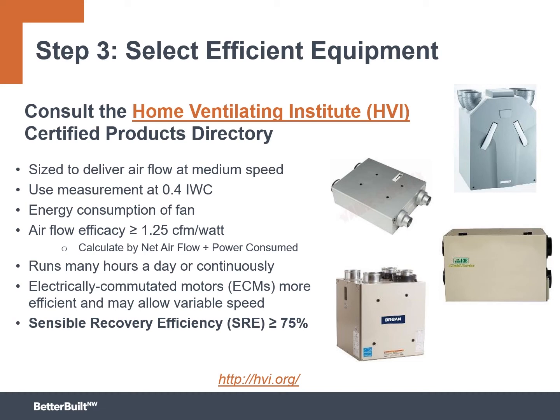Some considerations here. We want to size an HRV, specifically if we're thinking of continuous ventilation, to deliver the airflow at its medium speed. I'll show you in a minute how you can look that up. We can use measurements at 0.4 inches of water column. So essentially, we want to make sure that ducting has been done right so that that airflow selection makes sense. We do want to look at our fan energy consumption. That's also referred to as the airflow efficacy. And what we want is to get 1.25 cubic feet per minute for every watt of fan energy that we use. This helps make sure that the fan running constantly is not wasting a bunch of additional electricity.